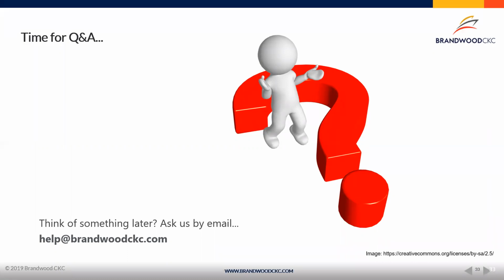Last question that we'll take is, can you provide an example of a risk control that can reduce severity? Severity is one of those interesting ones. Severity really cannot be controlled. If you've identified that your device could create hospitalization, and that's the highest severity risk, it's unlikely that any control you put in place, unless it's to redesign the device to eliminate that risk, will reduce the severity. So risk controls really focus on occurrence and may increase detection, but ultimately the intention is to reduce the probability of it occurring. Severity is really related to the harm.